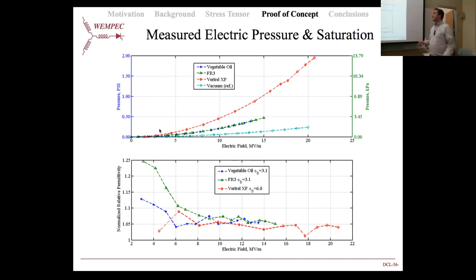And so there's an entire new area of chemistry that's opened up for this, because normally when you buy an insulating liquid, you don't want permittivity, because permittivity conducts flux lines. And so you want low permittivity, high breakdown strength. And that's something that usually the people that manufacture these are going for. They're not trying to actually make it with high permittivity. And so that's one of the challenges, but also at the same time an opportunity.